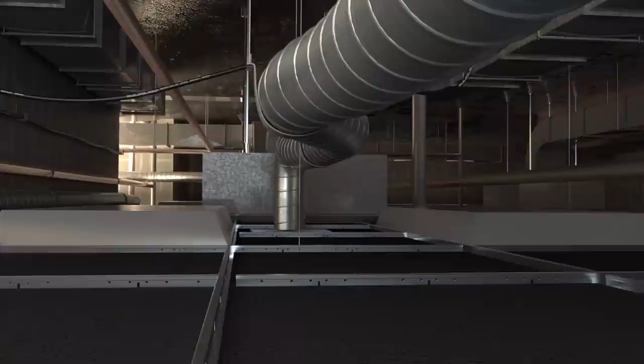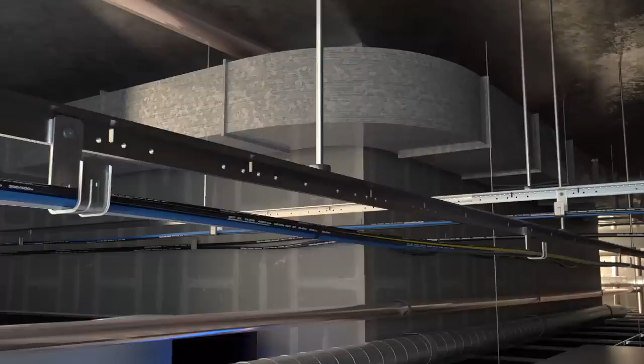One of the things you want to take a look at when you're at a commercial location, especially with installing cable, is that you don't want to hang that cable off of other trades. The other trades are things like your sprinkler system, the HVAC ducting, or any of the electrical lines. Always make sure you're having your own dedicated support for your cables. Plan that out, make sure you have good clean paths and aren't hanging up on anything. And make sure you're doing proper bracing and seismic support for anything you install, your racks, your cable management.